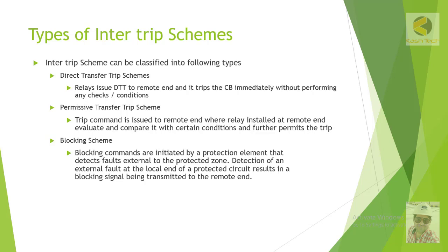Whereas in the Permissive scheme, the permissive signal is sent to the remote end indicating that the other end should trip. However, as we will discuss in detail later, the local end will evaluate certain local conditions that must be fulfilled in order to release the trip signal at the remote end.